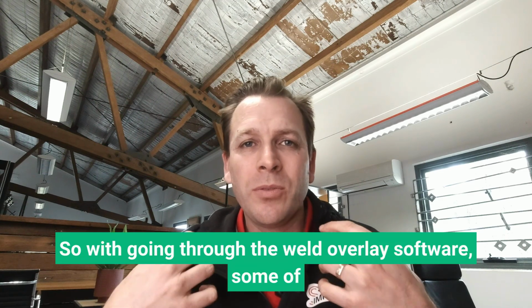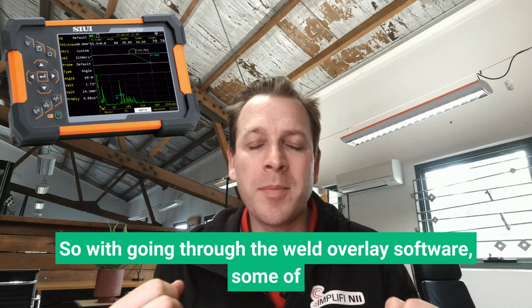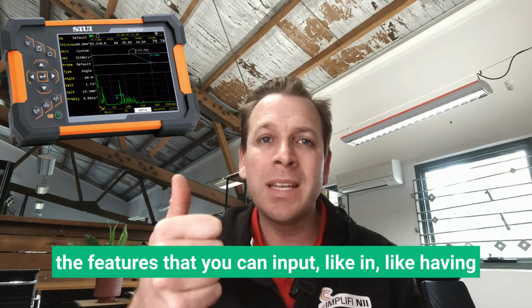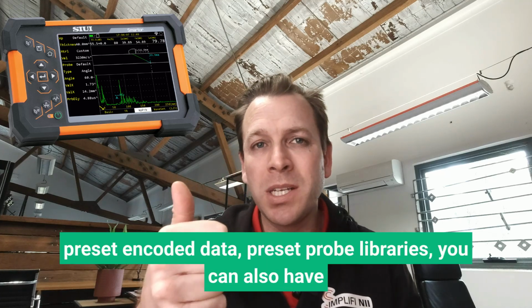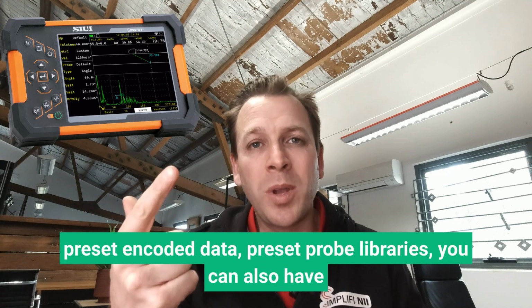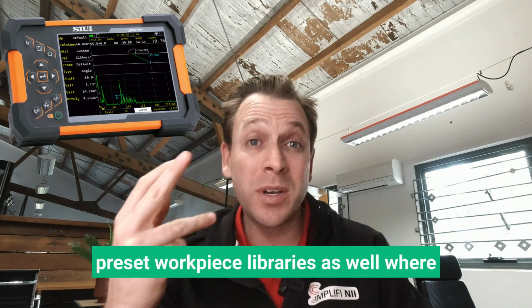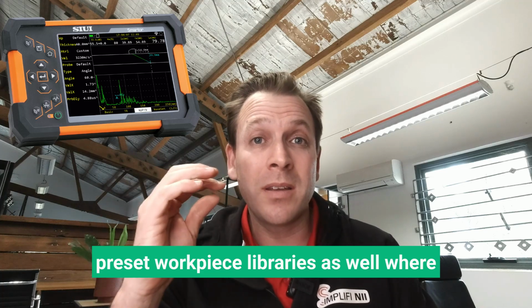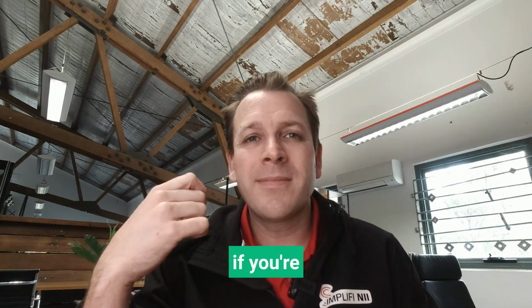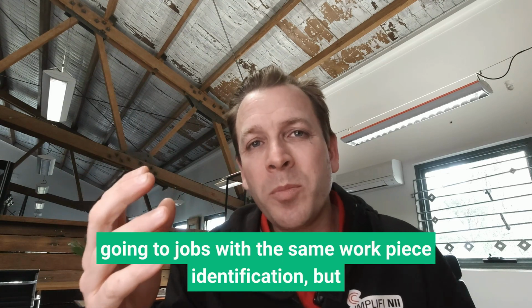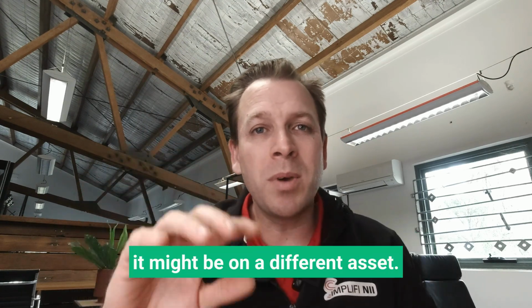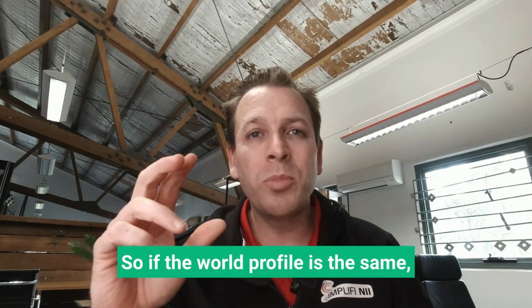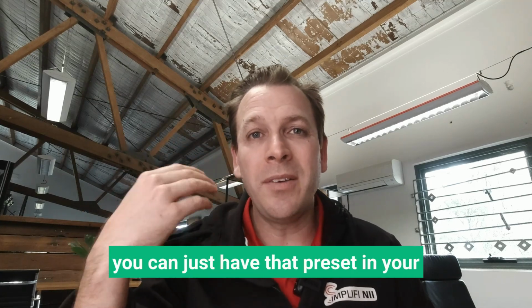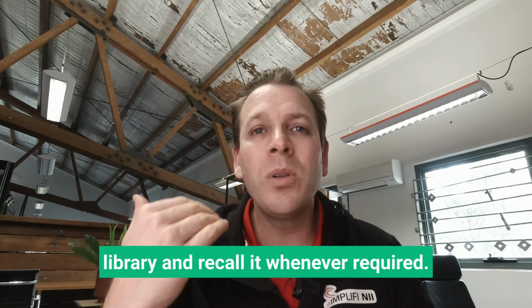So with going through the Weld overlay software, some of the features that you can input are having preset encoded data, preset probe libraries, and you can also have preset workpiece libraries as well. If you go into jobs with the same workpiece identification, but it might be on a different asset, and the weld profile is the same, you can just have that preset in your library and recall it whenever required.